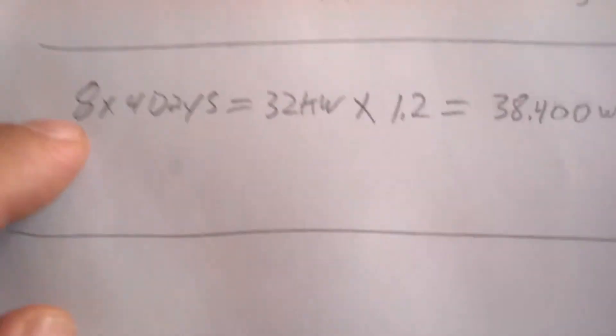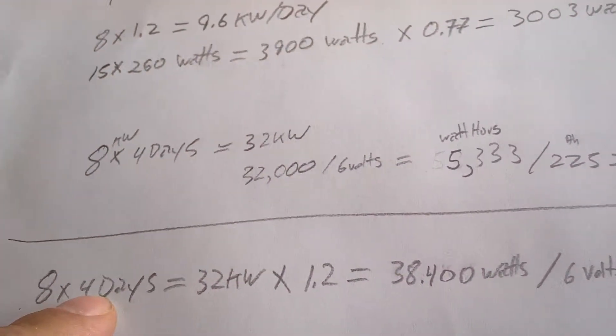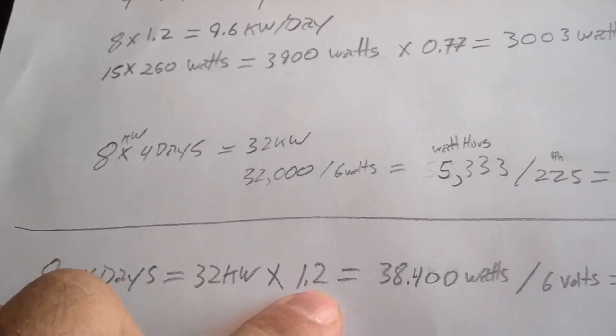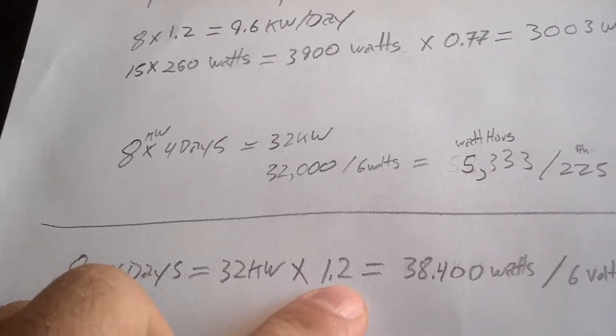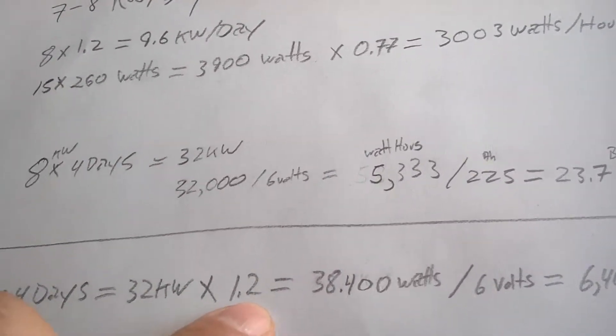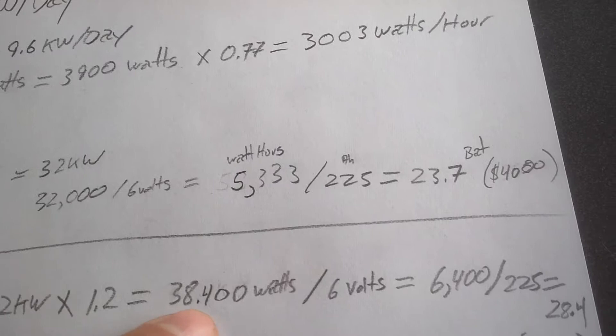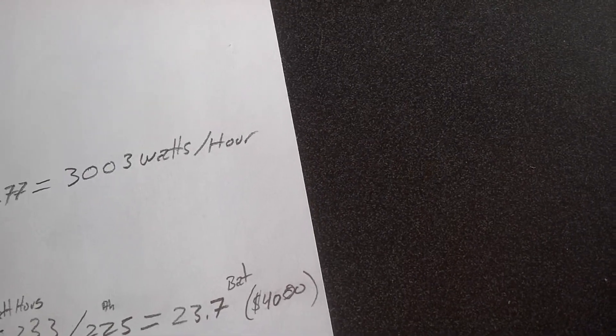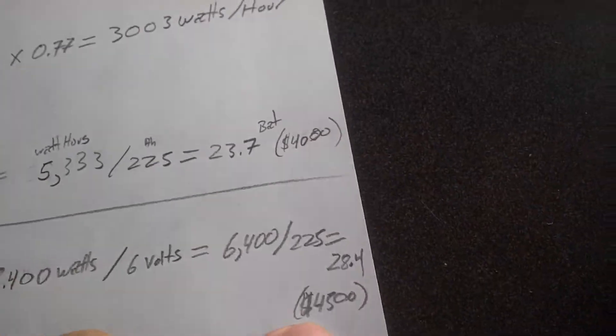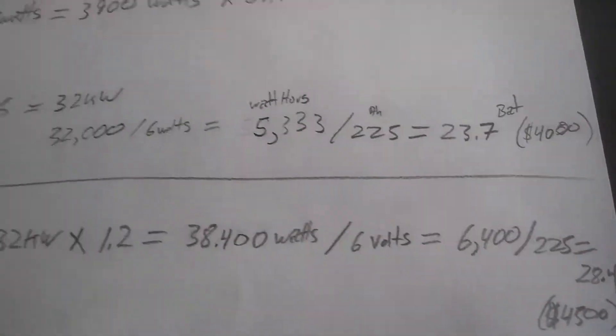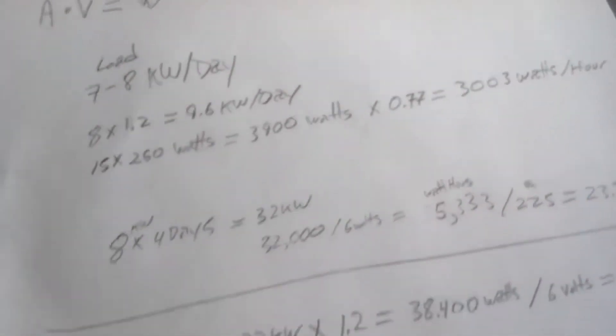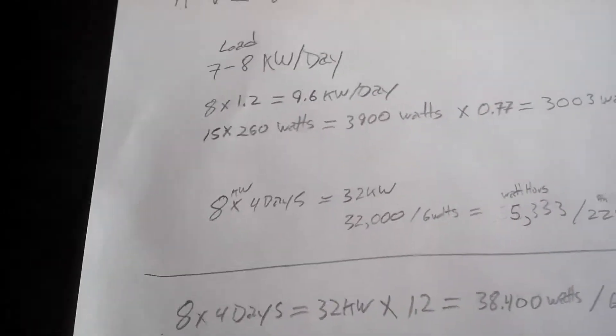So what we really have to do is do the same thing here, where we go 8 kilowatts times four days equals 32 kW, but then we have to multiply it by 1.2 for that 20% loss that we lose going from the charge controller into the batteries, then out of the batteries, back into the inverter, and then to the appliance. So we come up with 38,400 watts divided by 6 volts, 6400 divided by 225 amp hours, comes out to 28.4, or call it 29 batteries. So now we're talking $4,500. You say, well, that's not bad. Well, here's where it gets really bad. This is all assuming that you get a full battery and you run it flat dead, which for these types of batteries are the worst things that you could do, probably for almost any type of battery. But anyway, for these we know that to be the case, that that's a really terrible thing.